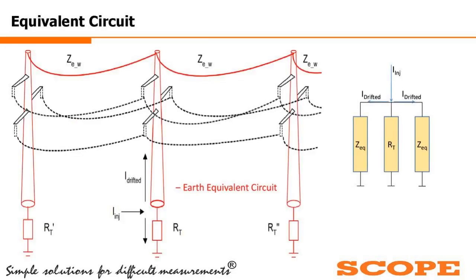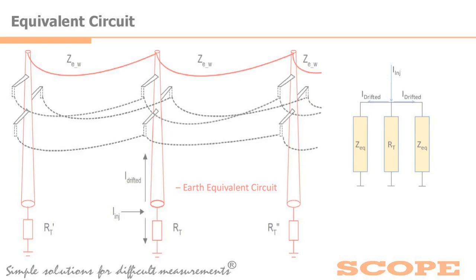Now, if we consider only three adjacent towers, and I want to measure the resistance at the center, I am injecting a current I injected. Whatever is going in the upward direction goes to the adjacent towers and to the ground through the virtual resistances shown as RT dash and RT double dash. So on the right hand side, we have created the equivalent circuit of the same.